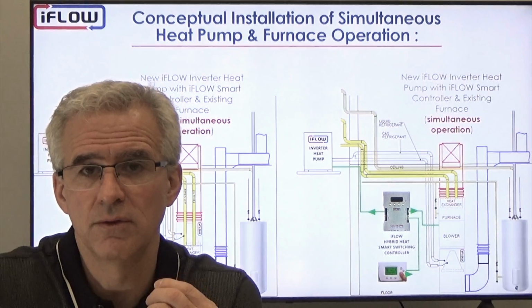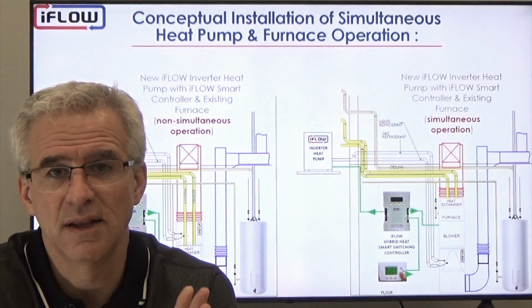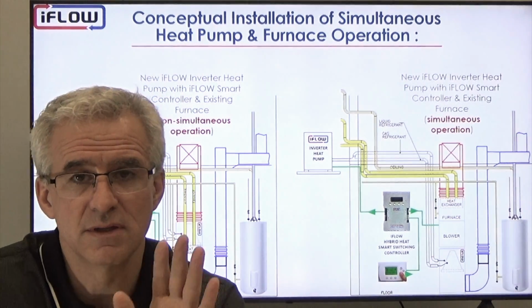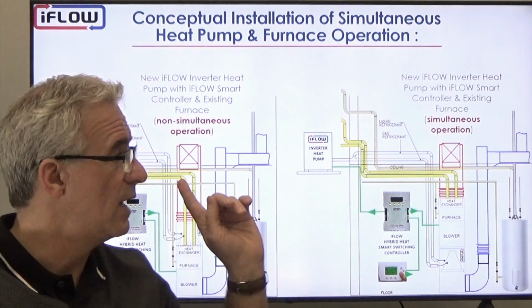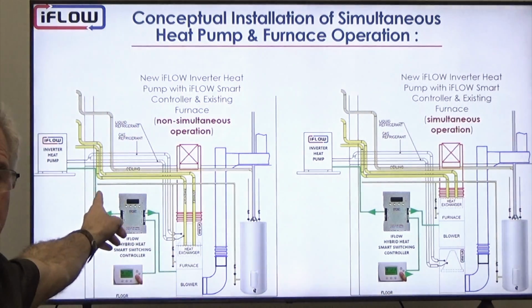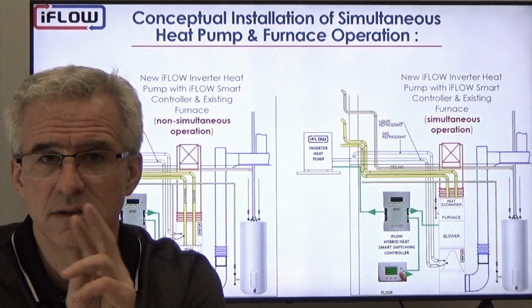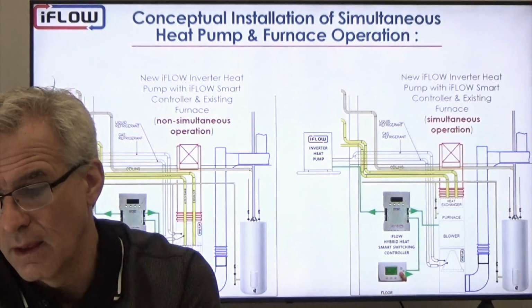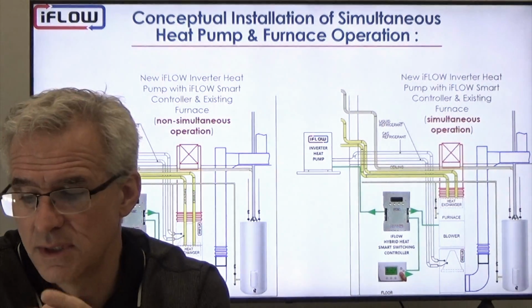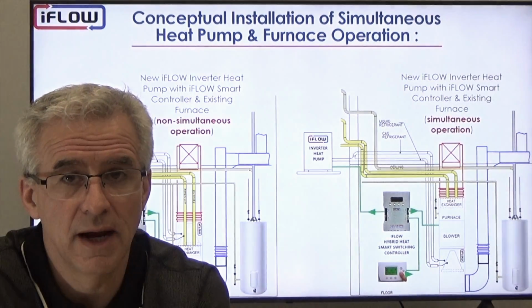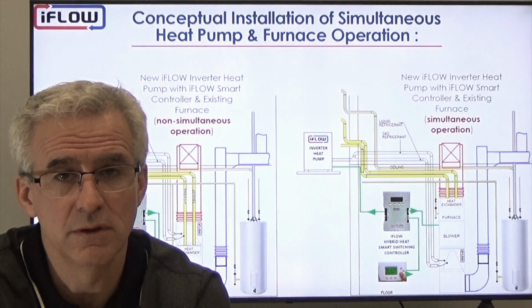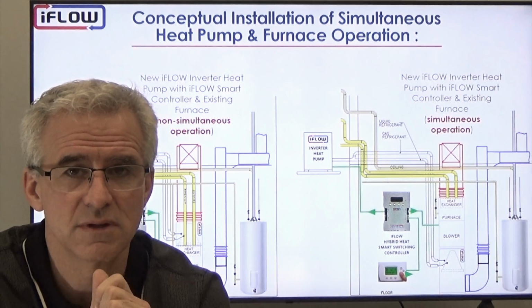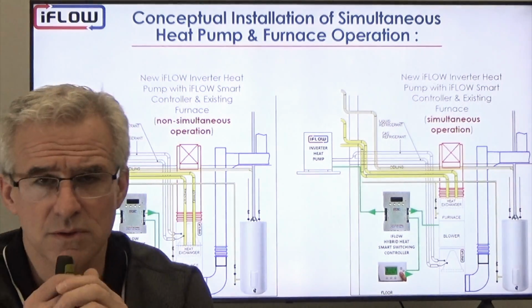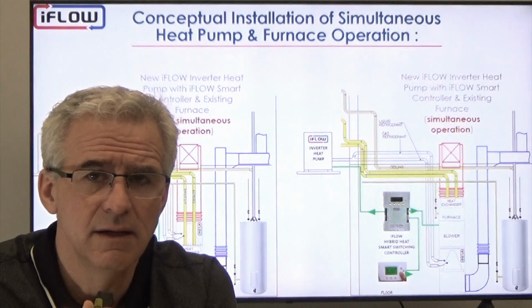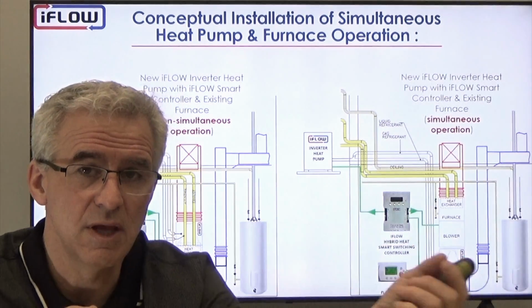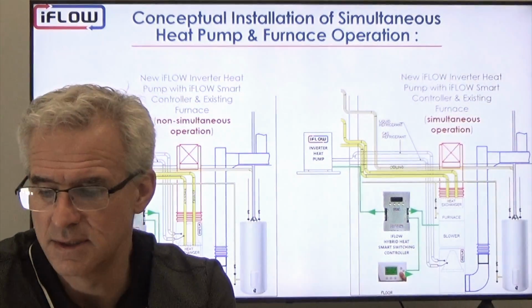There is a parameter that you set that will tell it the evaporator's location. The default is the evaporator on the supply, like the diagram on the left, but by switching that parameter, you will tell the iFLOW controller that you have the evaporator on the return side so that you can run both simultaneously. So on any call for heat, the unit will run both the heat pump and the furnace together.